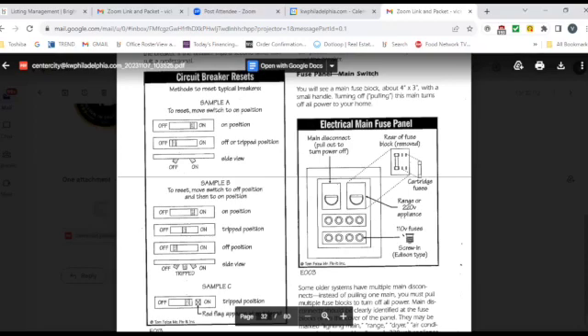Here's another type of reset you may see. The on position is on the far right, the tripped position is in the center, and the off position is all the way to the left. Move the switch to the off position and then to the on position. You run down the steps and look — everything is to the far right except this one, which is caught in the middle.